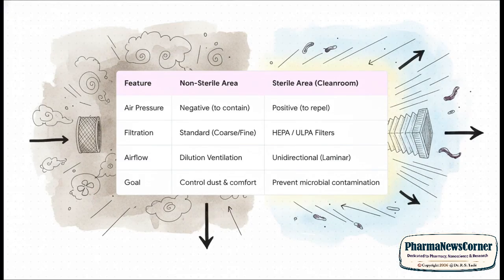Now, what's really interesting here is the direct comparison. In a non-sterile area, your main goal is dust control and comfort, so you're going to use standard filters. But in a sterile clean room, that's a whole different world. The goal there is to prevent microbial contamination, period. And that requires a totally different approach: strictly positive air pressure to literally push contaminants out, incredibly high-efficiency HEPA filters, and a one-way airflow to sweep any remaining particles away. The difference is truly night and day.